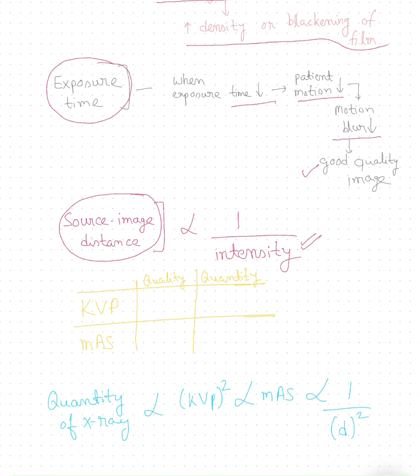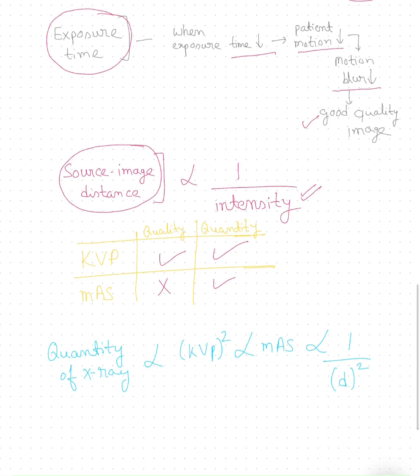From this video we learned that milliampere does not affect quality, while KVP affects both quality and quantity. The quantity of X-ray produced is directly proportional to the square of KVP, directly proportional to the milliampere second, and inversely proportional to the square of distance.